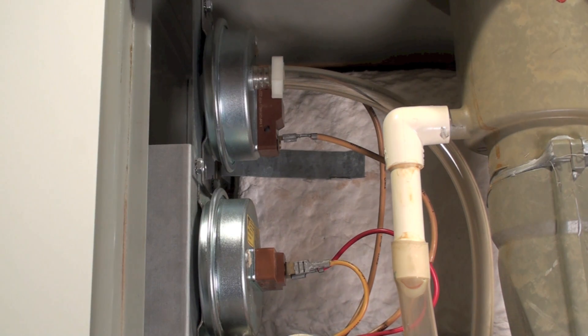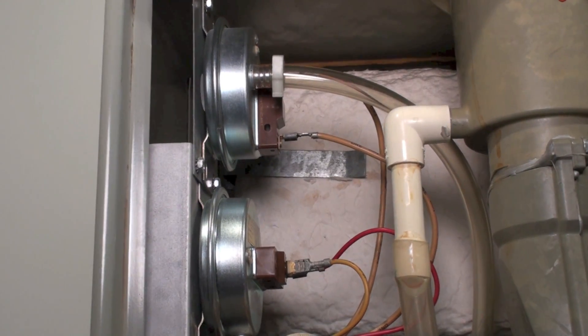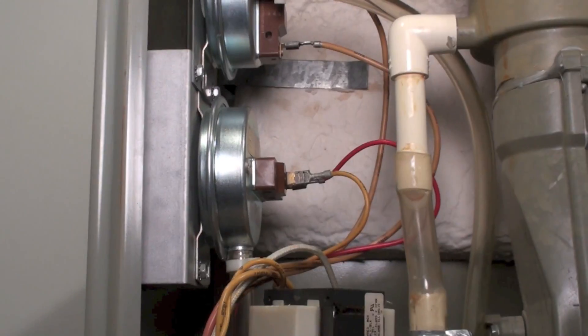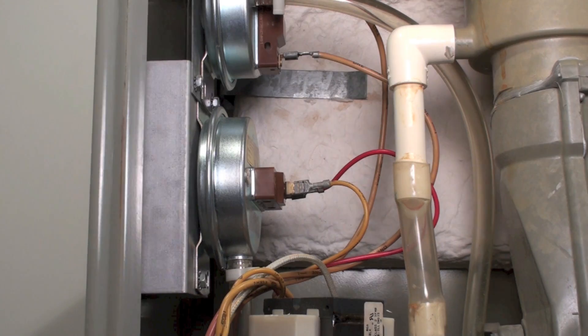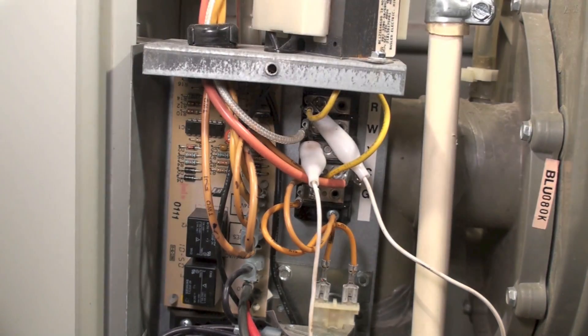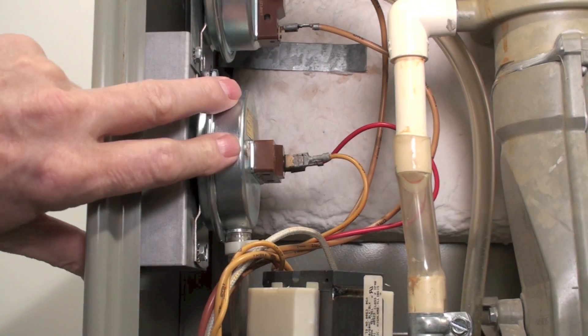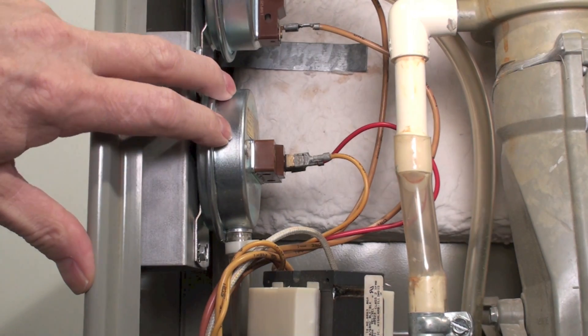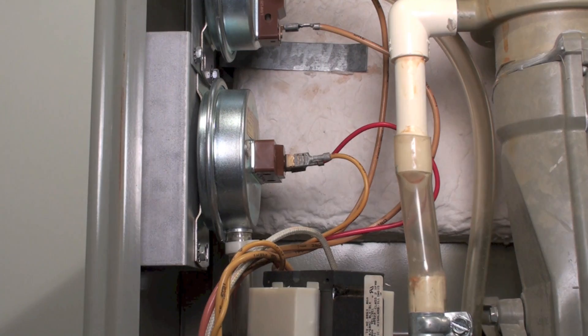The next one is the lower pressure switch. The lower pressure switch is hooked between the power source—and the power source at this point is down at this little board. When the vacuum on this pulls enough—now this one also pulls a vacuum, but it just goes down a little farther down the inlet pipe, closer to the secondary heat exchanger. When this closes, it transfers power down to the ignition control.